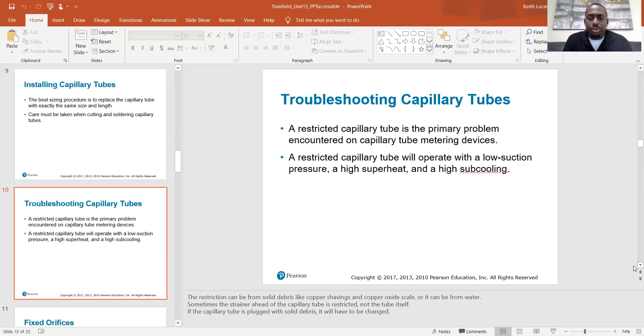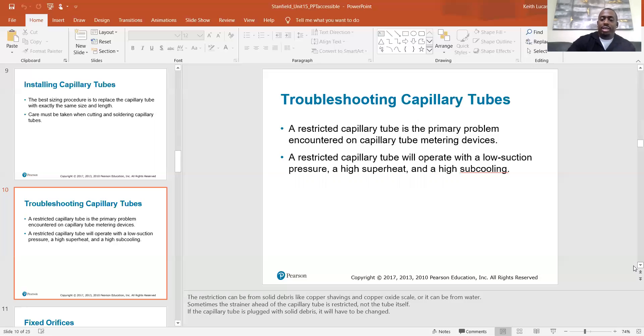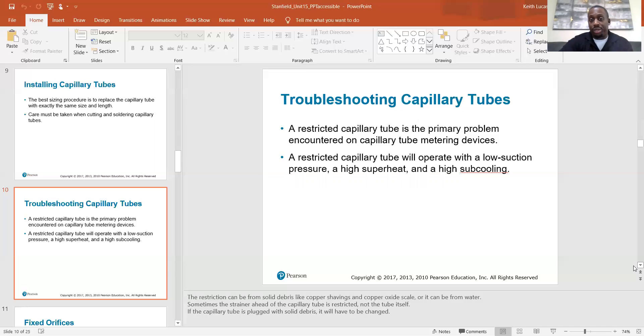A restricted capillary tube is the primary problem encountered on capillary tube metering devices. A restricted capillary tube will operate with a low suction pressure, high superheat, and high subcooling — those symptoms are a dead giveaway. The restriction can come from solid debris like copper shavings and copper oxide scale, or from water. Sometimes the strainer ahead of the capillary tube is restricted, not the tube itself. If plugged with solid debris, the tube will have to be changed. On some systems, you can pop off the strainer and rinse or replace it — it may just be doing its job, catching particulates before they clog the metering device.